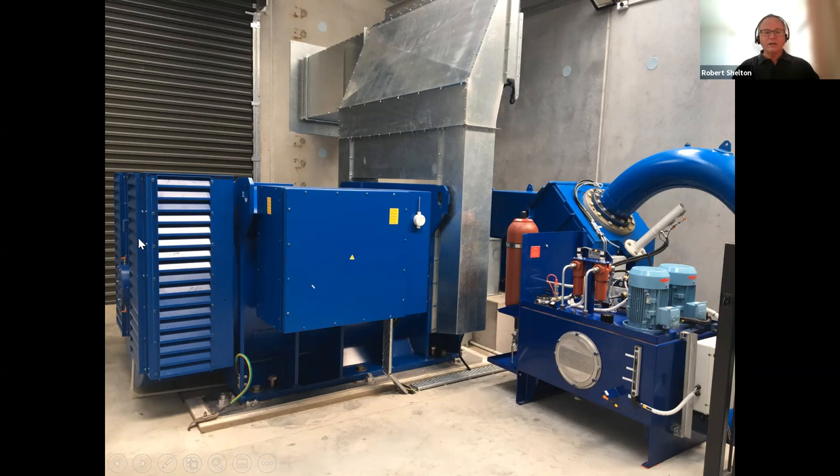Good air inlet here, some very nice louvers on the side of the building and ducted air out of the building. We've put some sensors on this air so that we can keep the building very clean with the ducting coming in. The temperature ranges on this power station go from about minus 10 degrees up to plus 30 degrees. So we have this ducting thermally controlled to keep the powerhouse at a maximum of about 28 degrees in the middle of summer and a nice 18 to 22 degrees in winter.